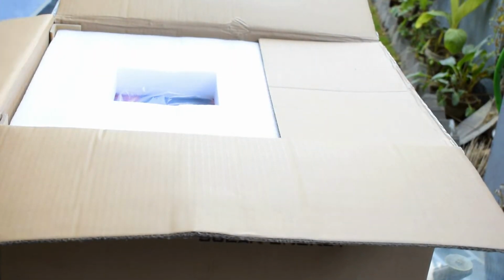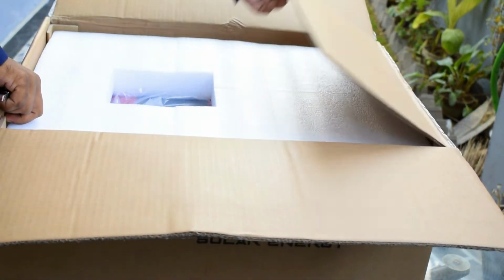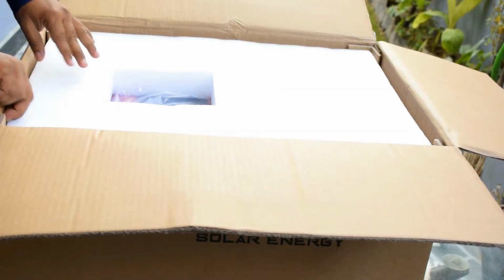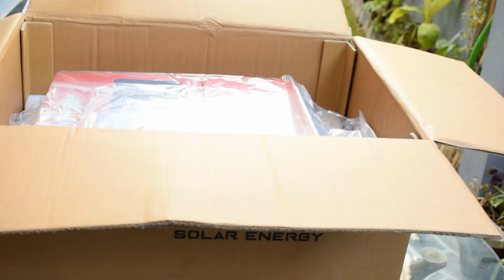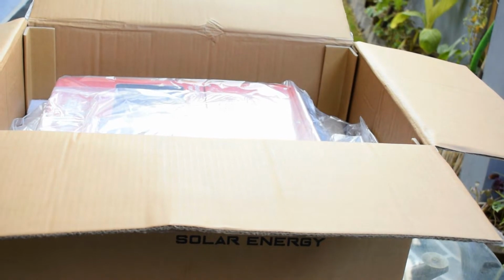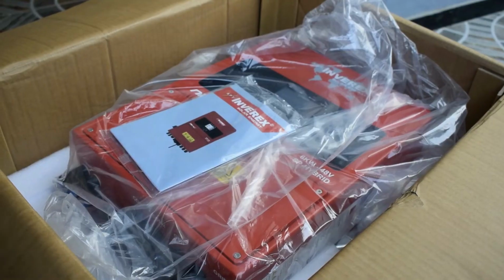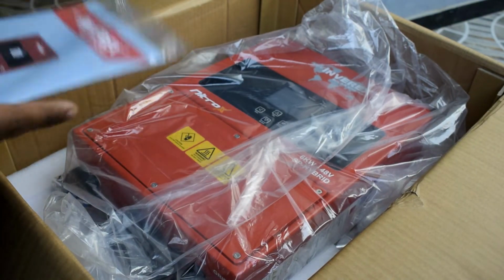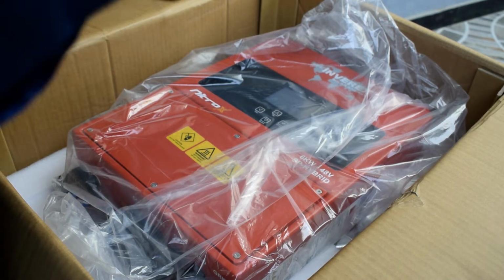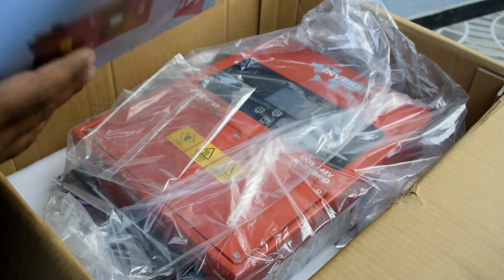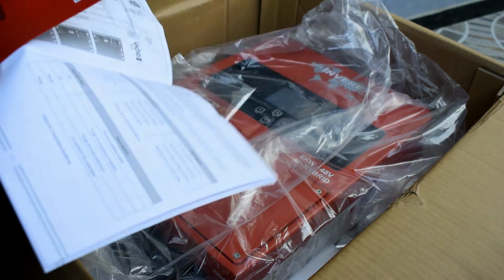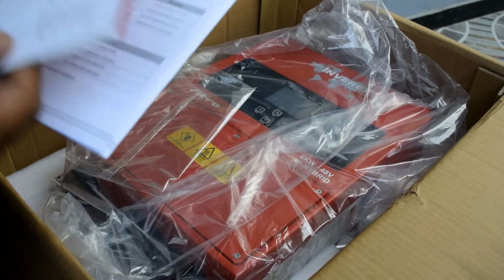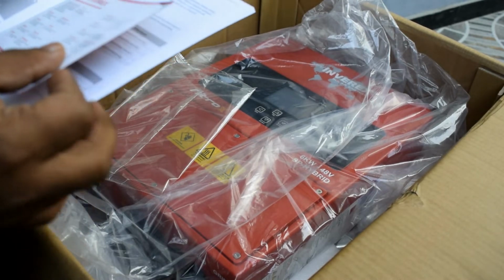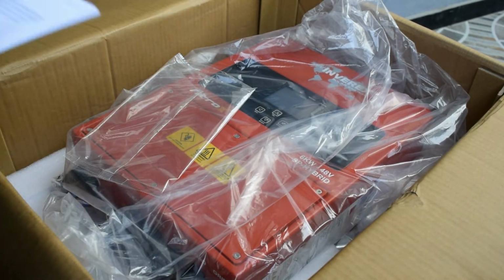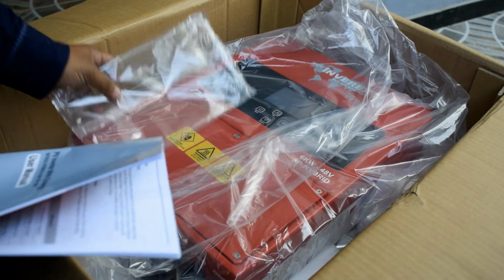Here we utilize this inverter as an off-grid inverter, not a hybrid. We cannot do reverse metering because it's single phase. So this is the Inverex 6 kilowatt hybrid inverter. Actually, the manufacturer is Chinese, and they only give the inverter to the Inverex company. We cannot import it directly from the Chinese manufacturers. It's a very good quality inverter, and it's IP65.